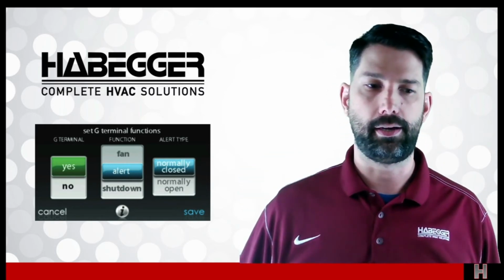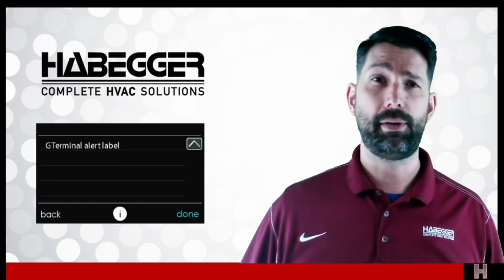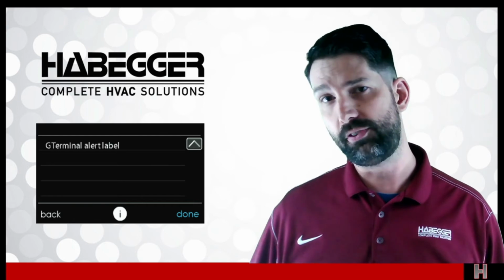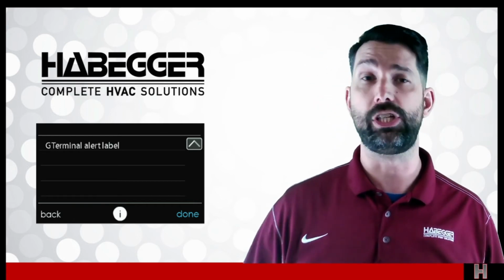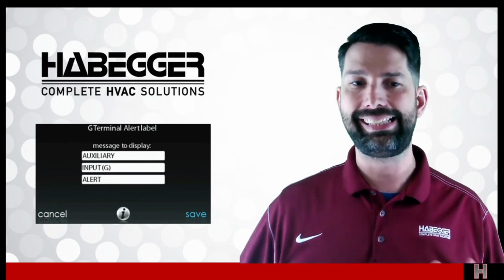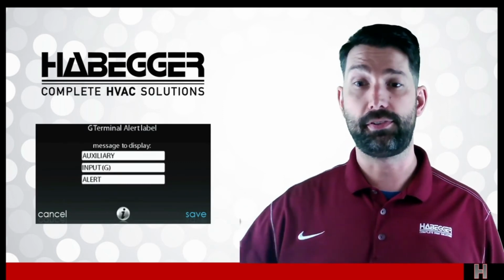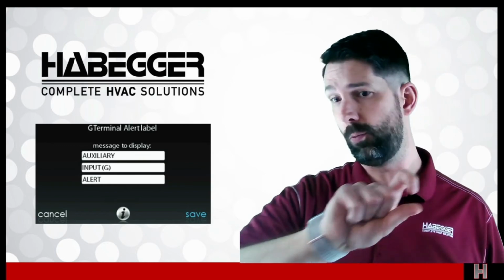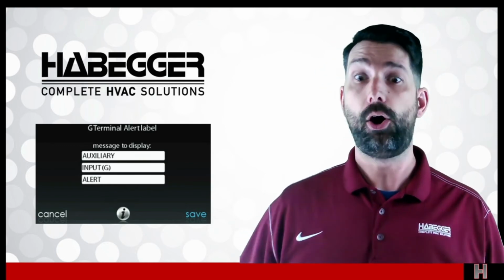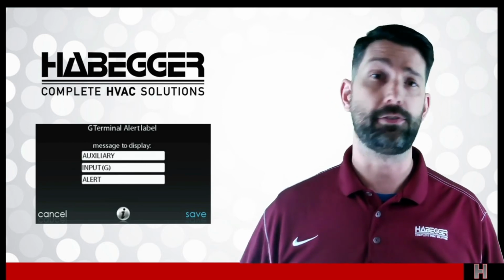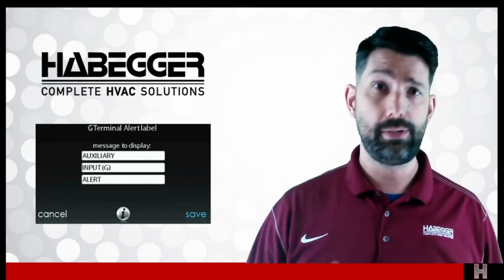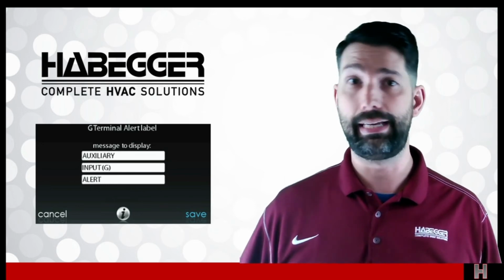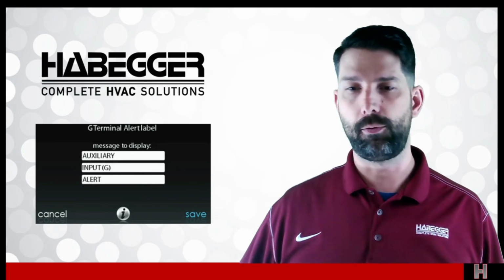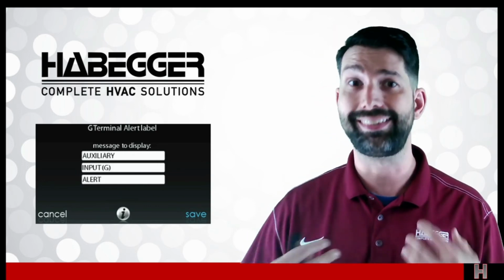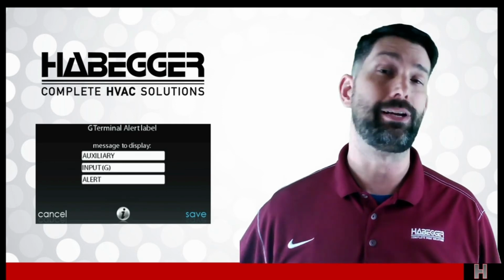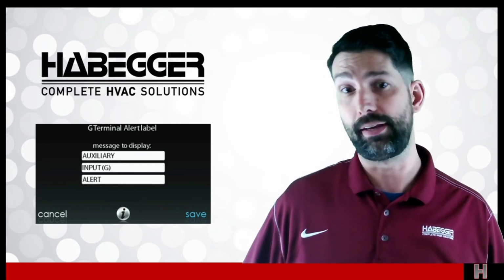So I really like the versatility of this function, and what I like about it most is you can actually label it. So if you save that and then back out and scroll down to the G-Terminal alert label, you can actually label that alert. So when the system does shut down with a water event, you can say water sensor alert, letting the homeowner know right from that user interface or thermostat that, hey, we've got a water issue, you need to call for service. You can really label those anything you want. So depending on what accessory and what application you have and what you want to tell the homeowner during that event, or if that event occurs, you can customize it, which I think is great.